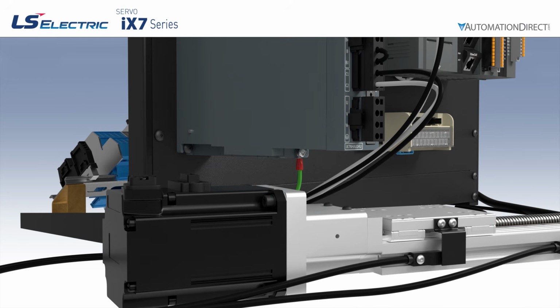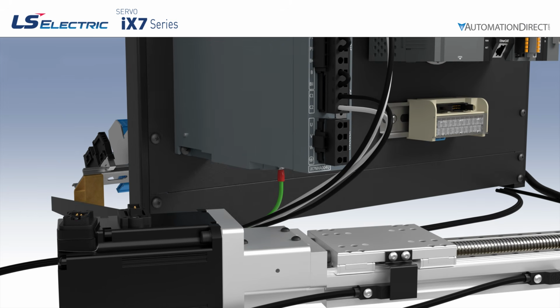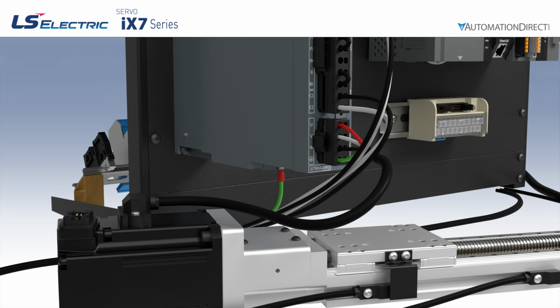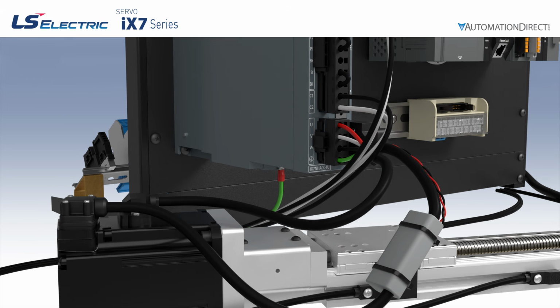Servo systems absolutely depend on solid grounding, even during initial testing. For motor wiring, connect the phases to U, V, and W, and connect the motor ground to the PE terminal at the bottom of the connector. Everything is color-coded and labeled, so pay close attention. Reversing a phase will cause an unrecoverable error until the phase is correctly connected. Connect the encoder to CN2.